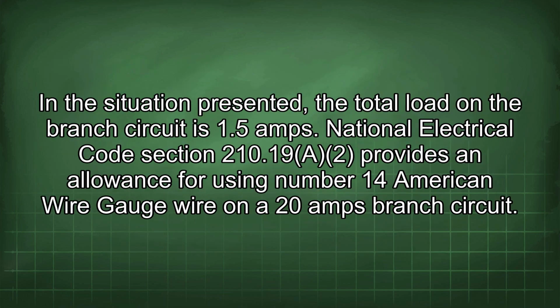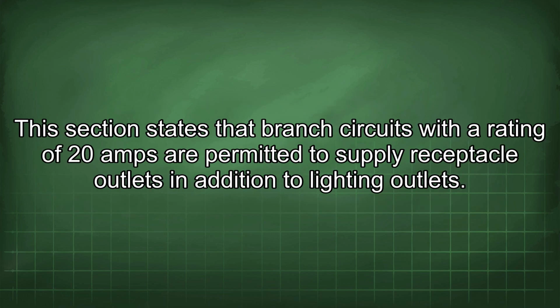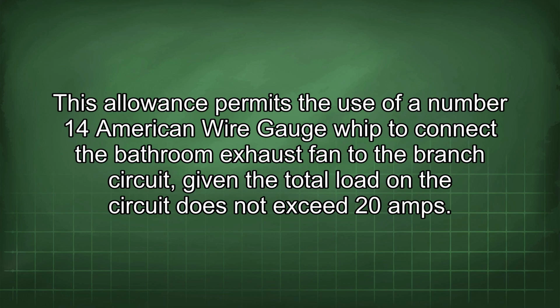In the situation presented, the total load on the branch circuit is 1.5 amps. National Electrical Code Section 210.19 provides an allowance for using number 14 American wire gauge wire on a 20 amp branch circuit. This section states that branch circuits with a rating of 20 amps are permitted to supply receptacle outlets in addition to lighting outlets. This allowance permits the use of a number 14 American wire gauge whip to connect the bathroom exhaust fan to the branch circuit, given the total load in the circuit does not exceed 20 amps.